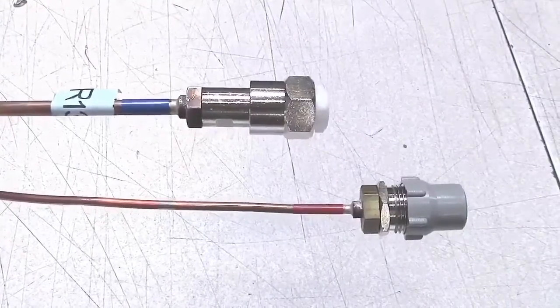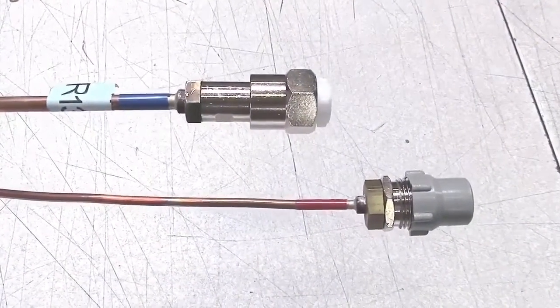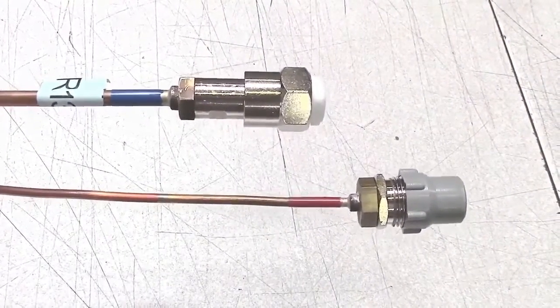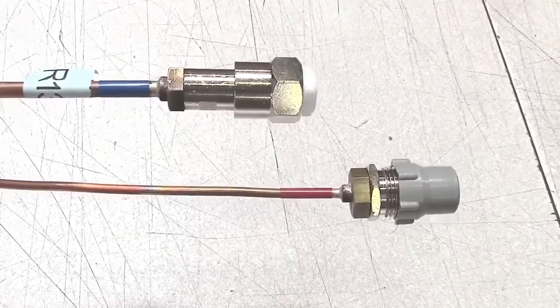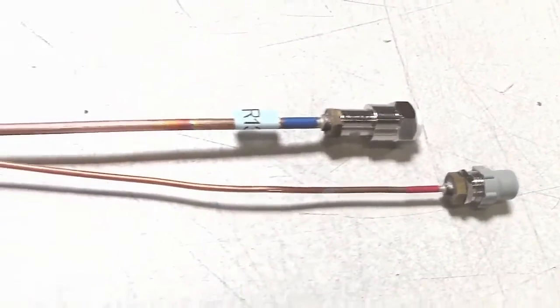At the end of every 10-foot line set on Frigoboat evaporators, there are two couplings attached to the tubes. The larger tube is the suction line from the evaporator back to the compressor — it carries the low pressure gas back to the compressor. The liquid line, the smaller of the two, carries the liquid under high pressure to the evaporator from the compressor condensing unit.